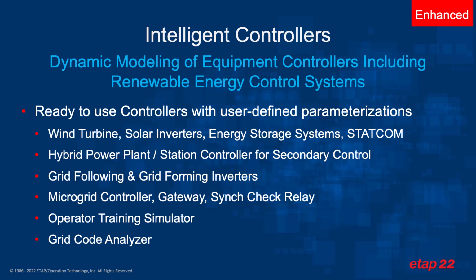These ready-to-use controllers with user-defined parameterizations are available for wind turbines, solar inverters, energy storage inverters, and STATCOMs, but they're also available for secondary control systems such as a hybrid power plant controller or station controller, as well as a microgrid controller. For energy storage, you can use grid following and grid forming inverters, and you can also use grid code analyzer for renewable energy control system analyses. These controllers can also be used as a foundation for the ETAP OTS or Operator Training Simulator.